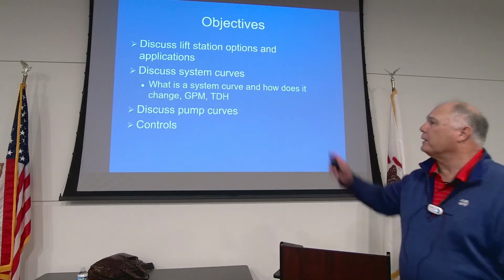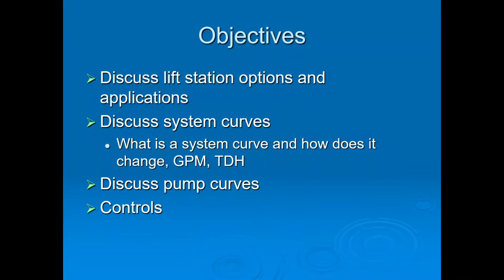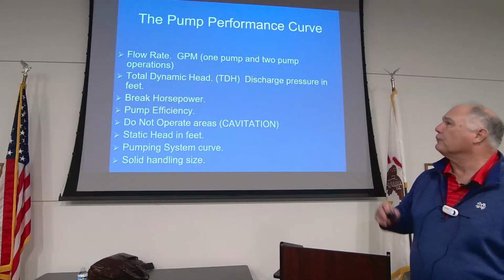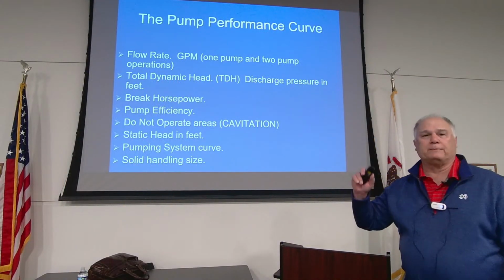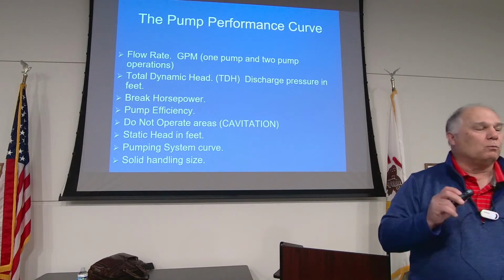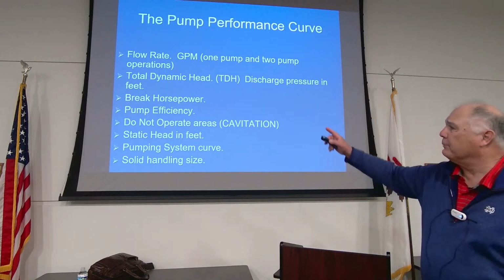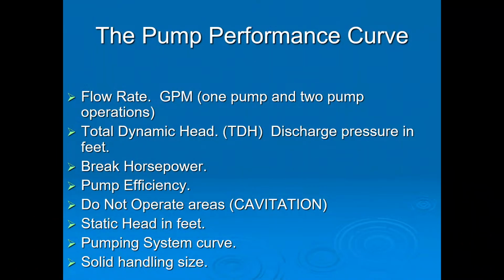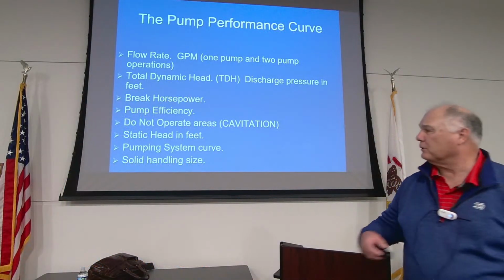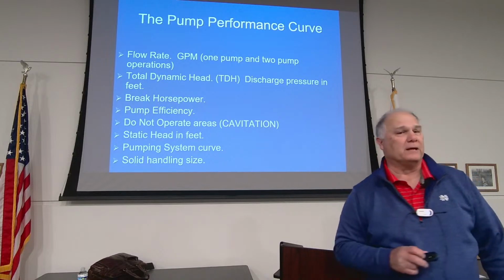So we're going to talk about system curves and pump curves and those types of things a little bit in this conversation today, and GPM. The first thing we talk about is how many gallons a minute that station needs to run. What's the head? What is the brake horsepower? What's the cavitation? How many people have ever heard of cavitation? Yeah? How many people have seen it? Okay? We're talking about static. We're going to talk about solid handling size and all that type of stuff.